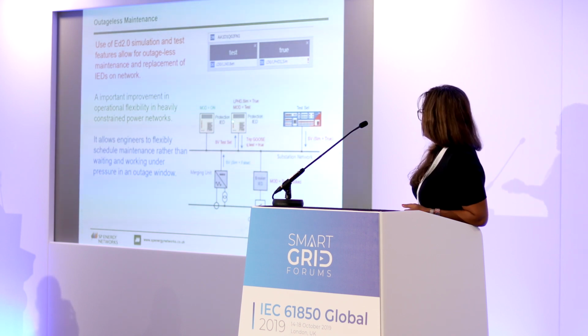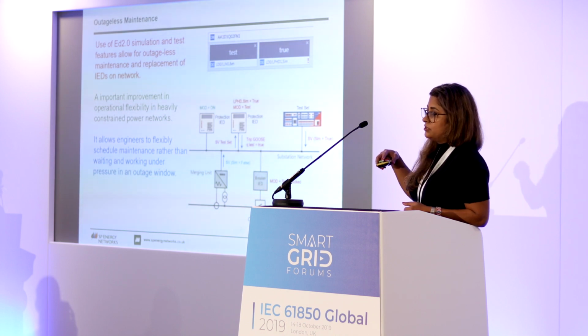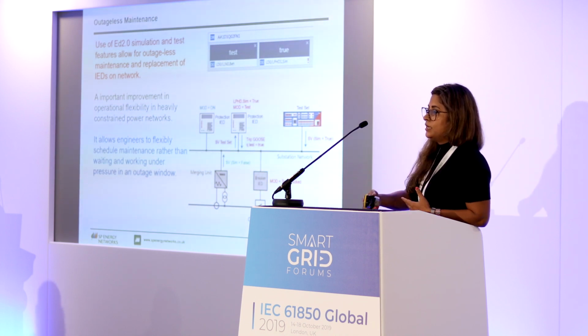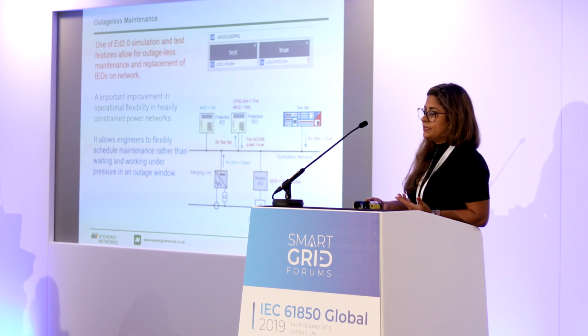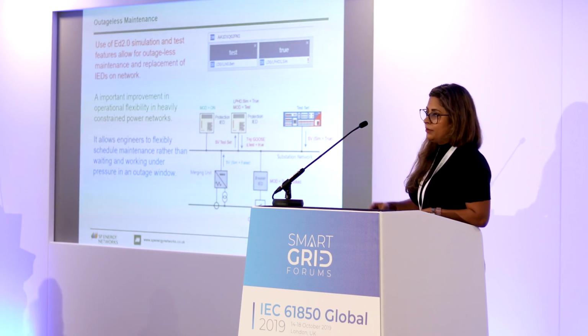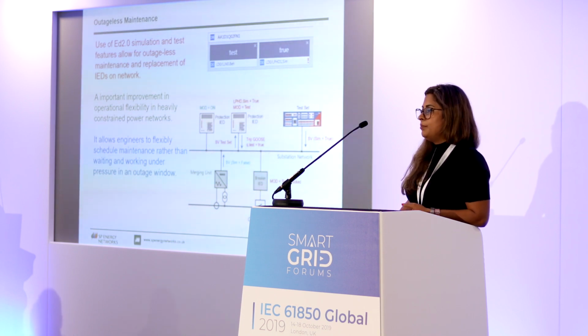Once you finish your test, as I showed in the automated test regime before, you take all the flags out, and if you need to replace the IED, you replace it. If not, you put it back into operation. It's a really powerful feature. We commissioned our entire substation, our entire protection system using this, and I cannot recommend it enough.